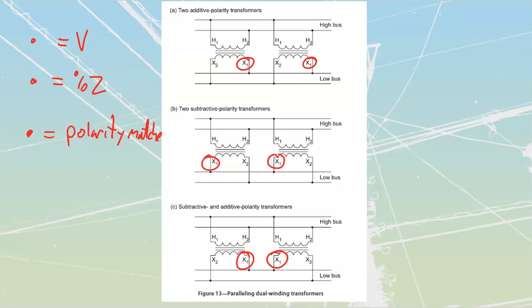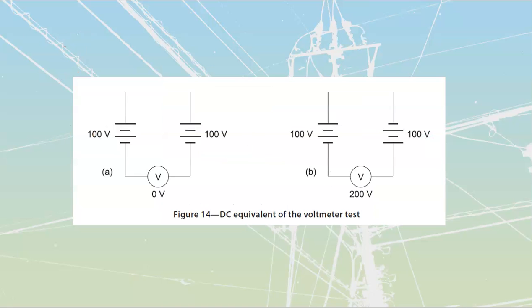When we do these tests, there's a way to double check that we've done it correctly. One way is to do what's called a voltmeter closure test. This is where I hold off on doing my final connection and check my voltage value with a voltmeter first. If it looks good, I close in. If not, I'm not going to bother closing in - I'll reassess what I've done and whether it's a good type of system. The voltmeter closure test is us taking a look at a partially done connection, just the last connection we're checking.